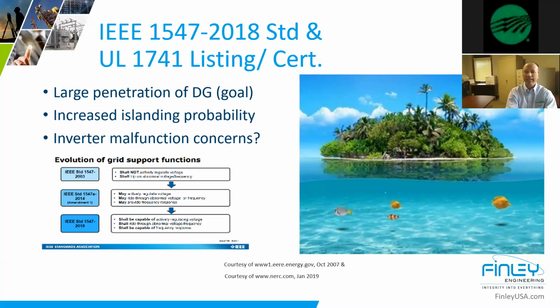I'd say so. Okay, the 18 standard came out and has said that a distributed generation system shall be capable of actively regulating voltage and shall ride through abnormal voltage, frequency, and frequency response. That's the three parameters they have talked about or added. So as of the 18 standard, now granted, a bolted fault is still going to make the inverter trip out. But the 18 standard is written so that the manufacturers producing products to meet the 1547 2018 version standard are trying to build the power electronics in such a way that they will ride through minimum level faults and try to actively regulate to hang on, if you will. That's the best analogy to do it.